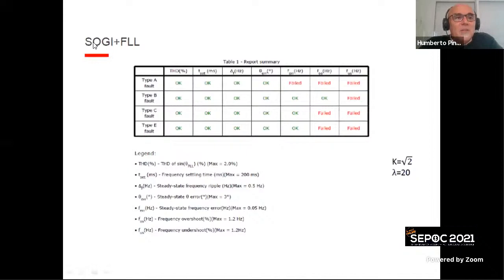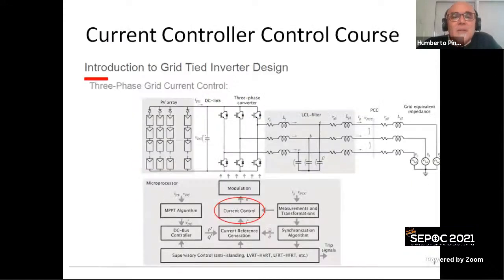Here, in this case, we are testing a second-order generalized integrator with a frequency-locked loop. We also have available on the site a Kalman filter for the synchronization algorithm, synchronous reference frames, PLL with positive sequence extraction, and so on. There are a couple of alternatives you can consider for the synchronization algorithm for grid-following converters.